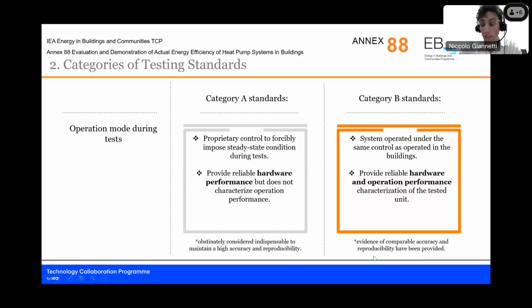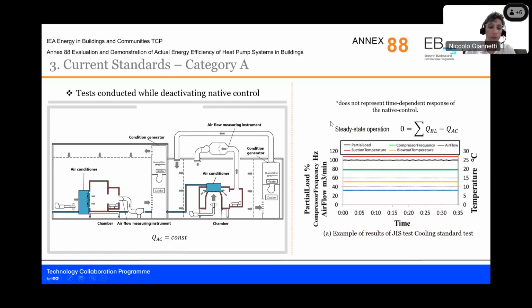Okay, and we already have evidence that this test can have a comparable reproducibility level and accuracy, and definitely higher representativeness of the result, when compared to category A standards. So starting with category A standards, we said that the system operates, in this case, in a forced steady state operation. In this test, the capacity supplied by the indoor unit is kept constant by fixing the compressor speed. And on the right side is an example of the test result that we can obtain during this kind of test.